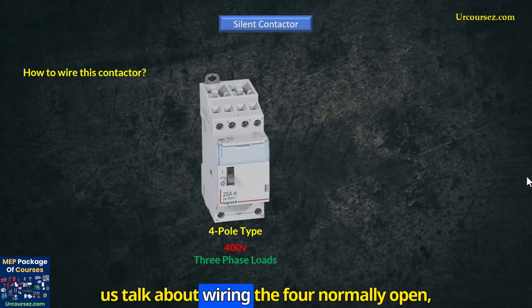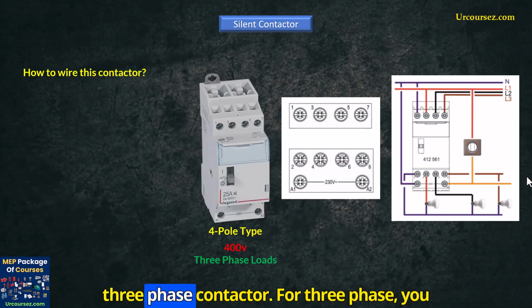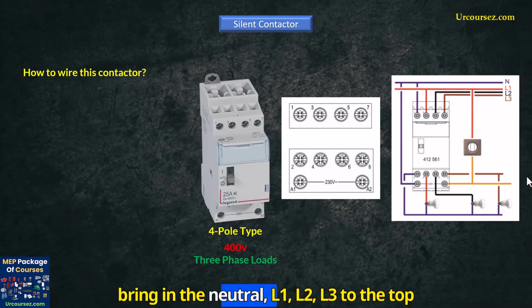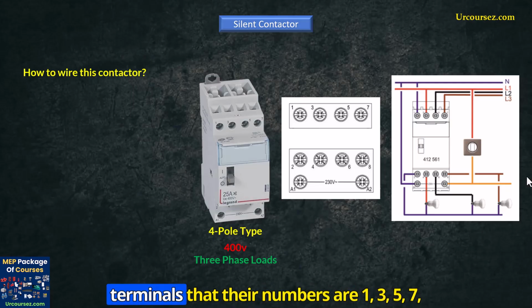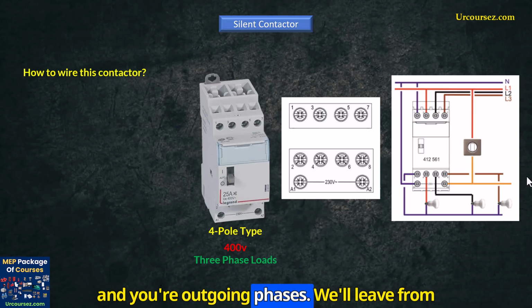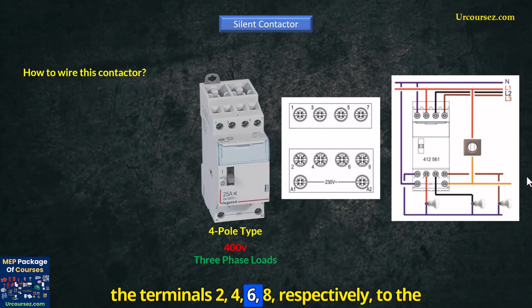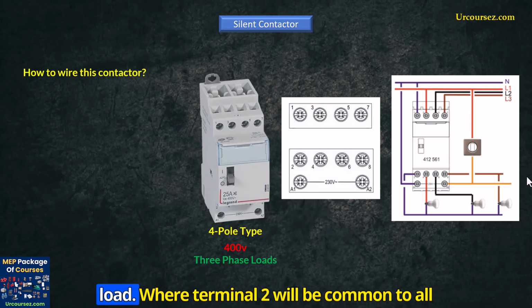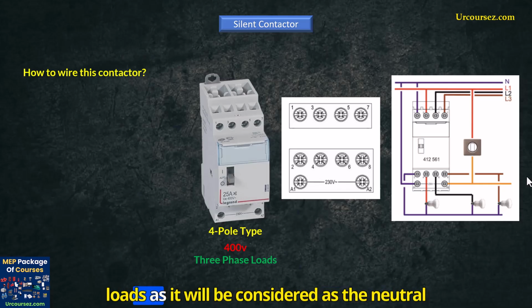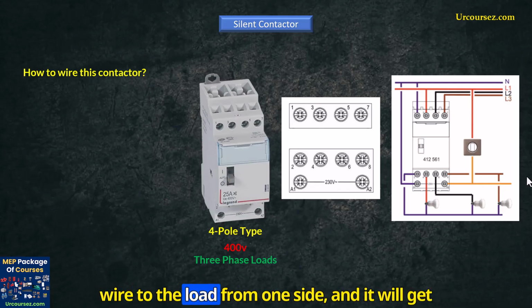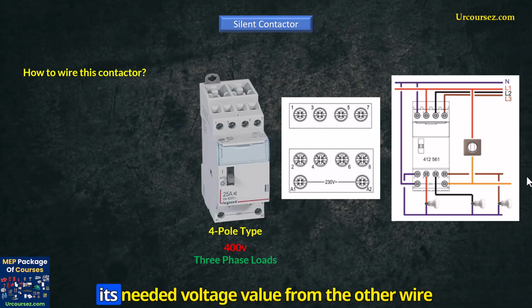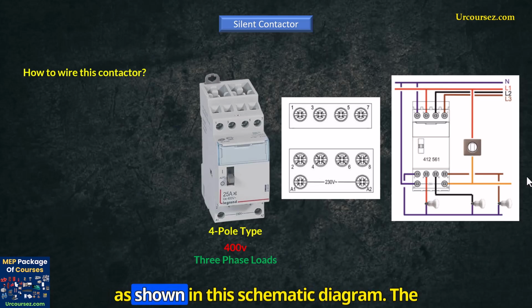Now let us talk about wiring the four normally open three-phase contactor. For three-phase, you bring in the neutral, L1, L2, L3 to the top terminals that their numbers are 1, 3, 5, 7, and your outgoing phases will leave from the terminals 2, 4, 6, 8 respectively to the load.